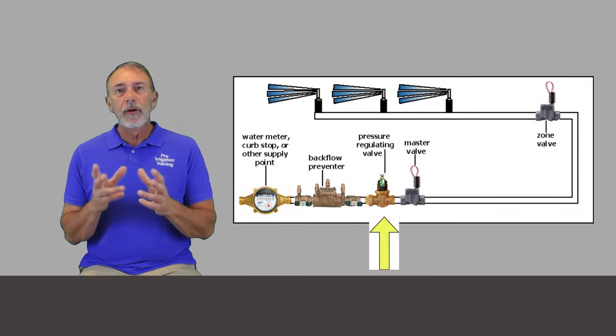So you should always have an isolation valve as your very first thing, so that really should be a backflow preventer or an isolation valve plus anti-siphon valves. Now beyond that, the next component would be a pressure reduction valve or pressure reducing valve if necessary. And usually my rule on that is if there's more than 75 or 80 PSI going into the irrigation system, I'll generally want to put a pressure reducing valve on it.